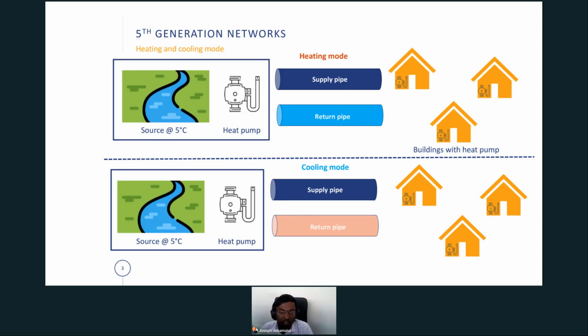The fifth generation systems can do both heating and cooling. In this case we have a source at about 5 degrees Celsius, so we have a centralized heat pump which pumps from 5 to 15 degrees Celsius. In heating mode, we have distributed heat pumps at each and every building. The supply pipe delivers ultra low temperature water, which heats the building and returns cold water back to the source.